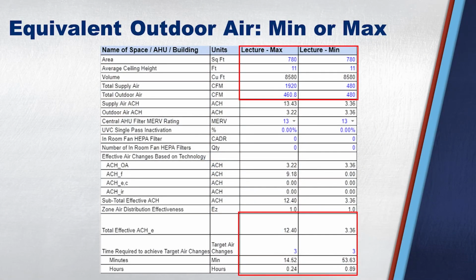So if I'm operating at minimum airflow, you might want to look at your trends to figure out where you really are. This is a lecture hall at a university, and the actual numbers from their air, and at minimum, they're essentially 100% outside air. And even though they have MERV 13 filters, at max airflow, they're doing 12 equivalent air changes per hour, which is really great. At minimum, they're doing 3.36. So where's your system actually operating? You can't just assume that it's at design, because we all know engineers have a lot of safety factor.